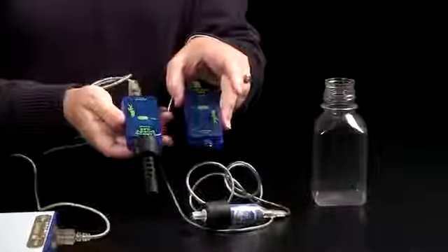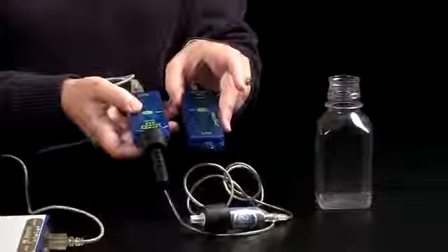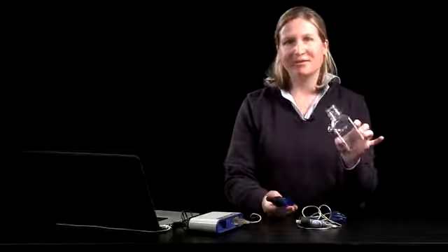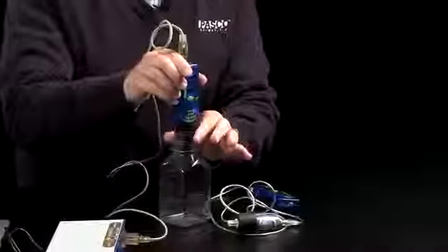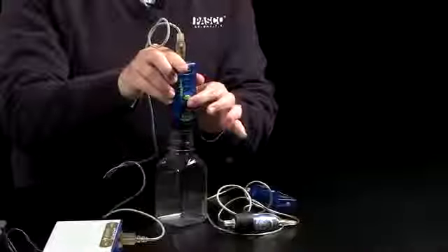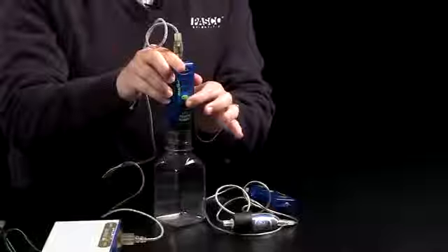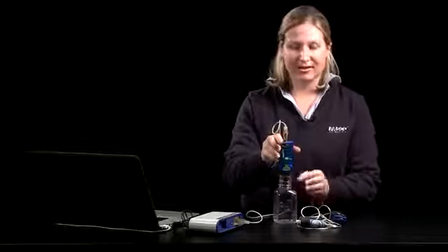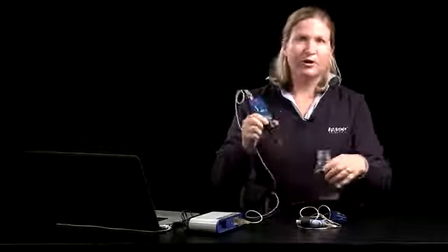The front of each of the sensors has a green calibration button, and you'll want to calibrate using an empty sampling bottle. Each of the sensors comes with the sampling bottle. You can plug the sampling bottle into the sensor, hold down the green calibration button, and when you see the flashing light behavior change, then you know that your sensor is calibrated. For each of the demonstrations that I'm going to show you today, I've already calibrated the sensors.